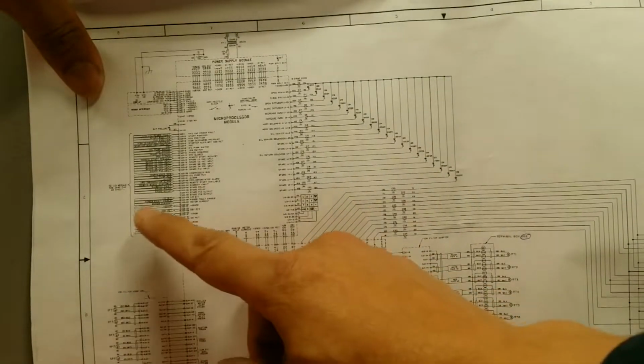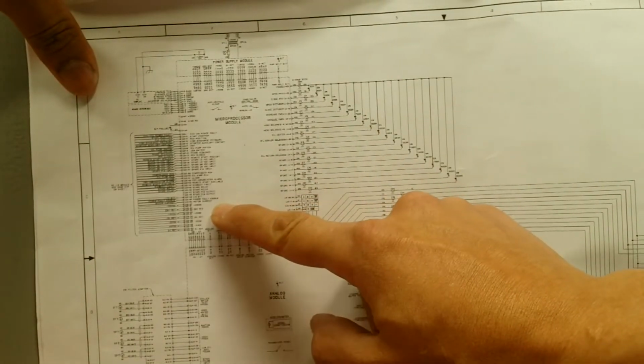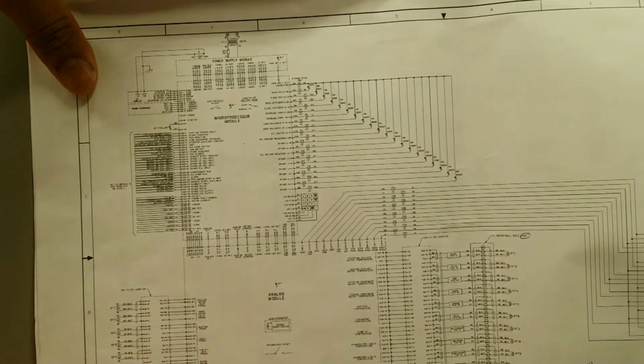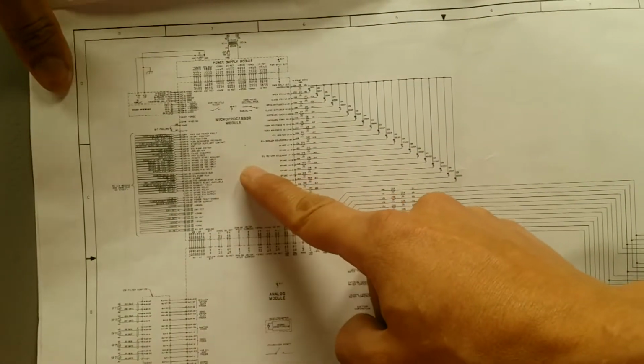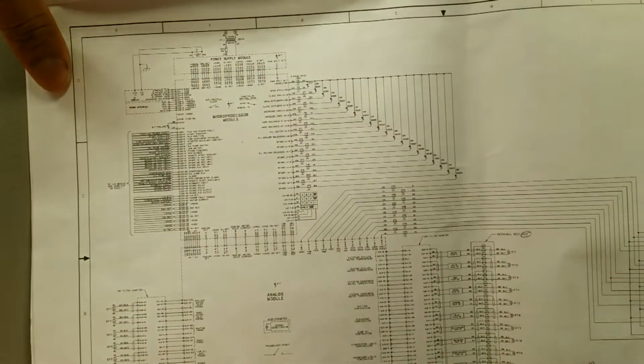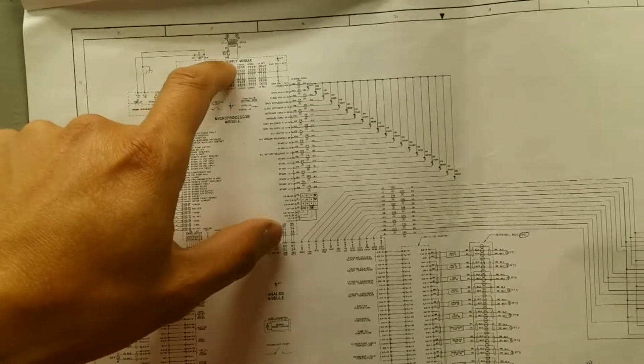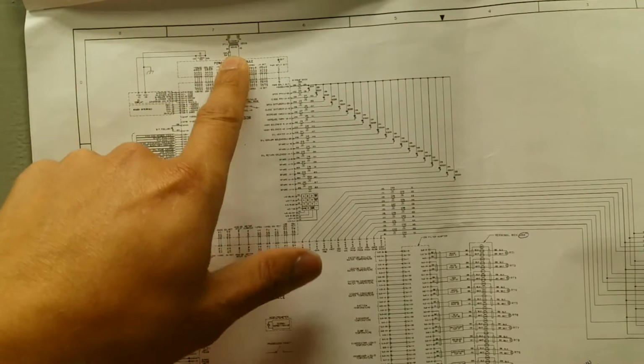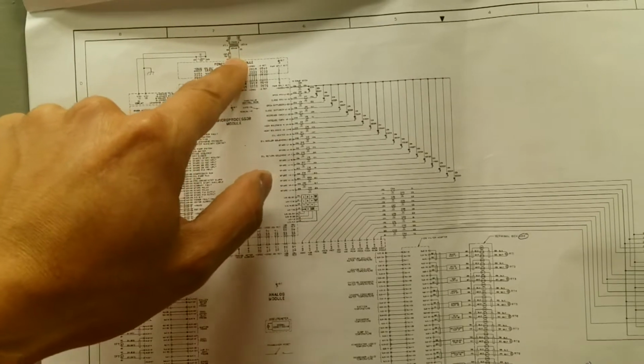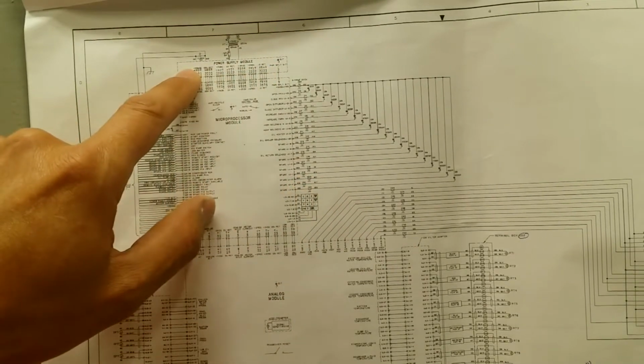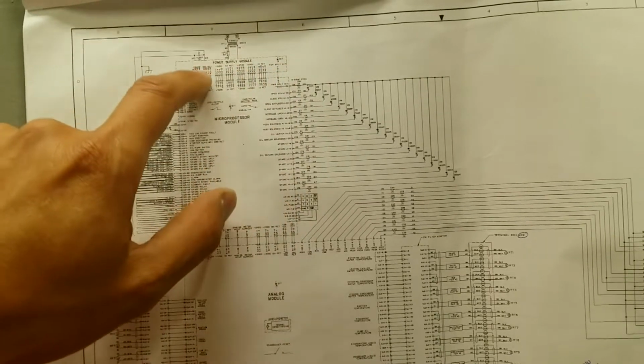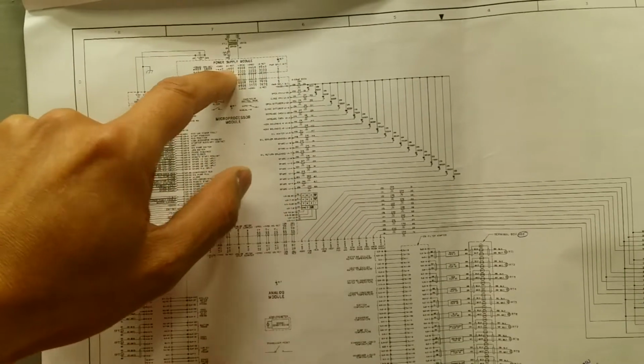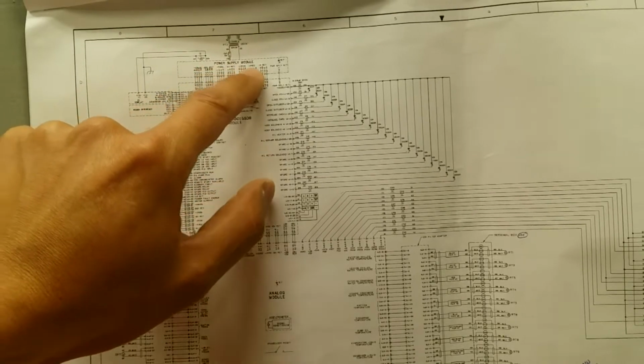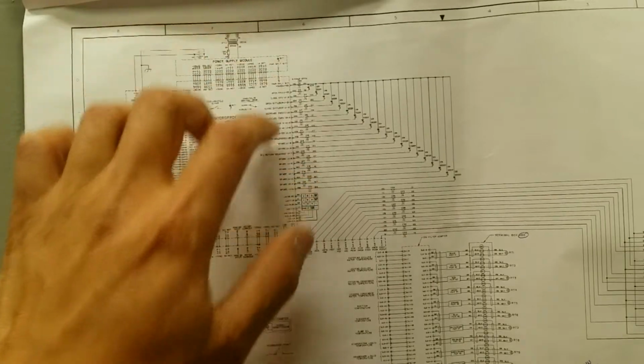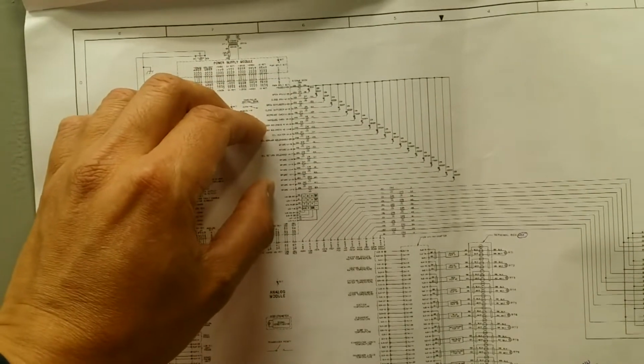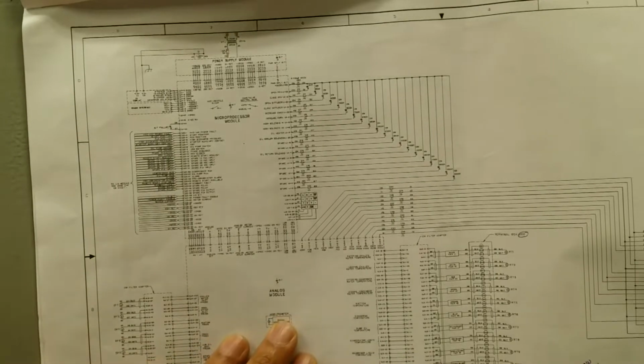Alright, so I did mention that the microprocessor module gives the voltages for the input and output module to function, but this card itself gets all these voltages from the power supply module. This is the module that I want to talk about next. If you can see, it has a transformer next to it with a fuse, and this card takes those voltages and creates your plus 28 volts, your plus 5 volts, and your minus and plus DC 12 volts. Then it feeds it to the microprocessor module, and this module distributes it to the other 2 modules, to include the analog module.